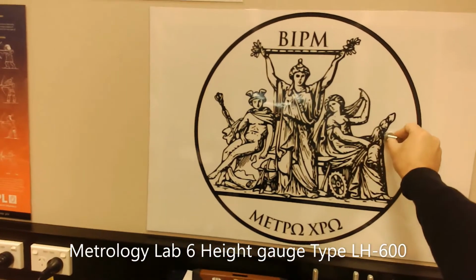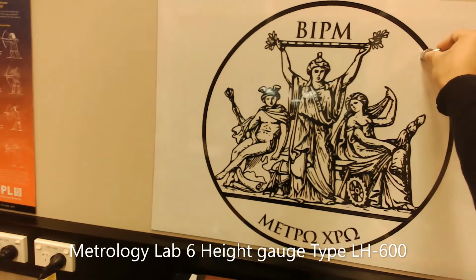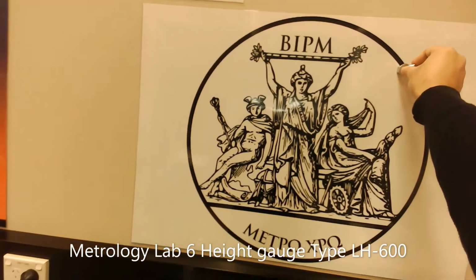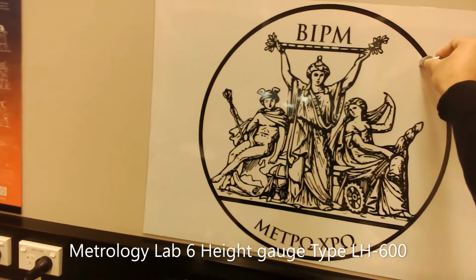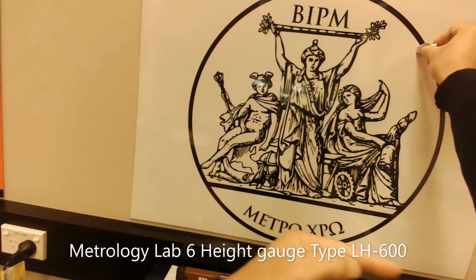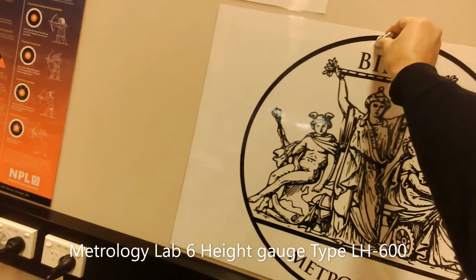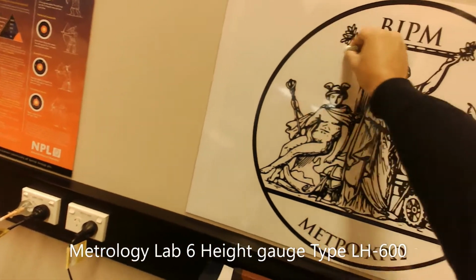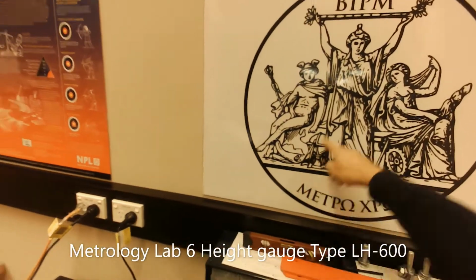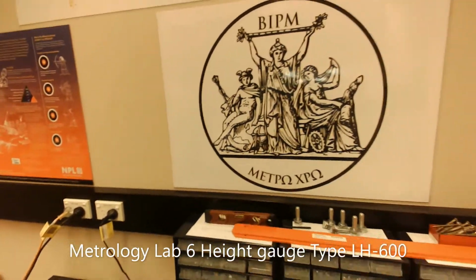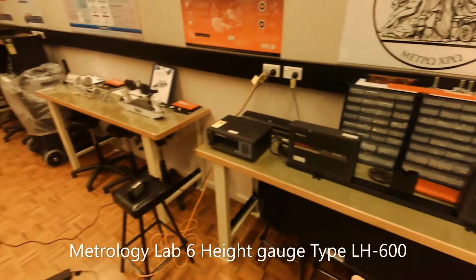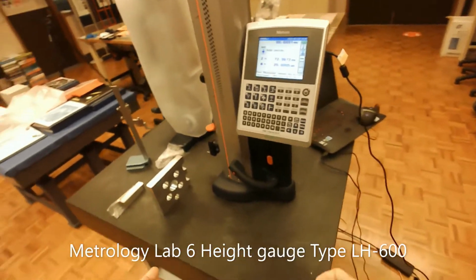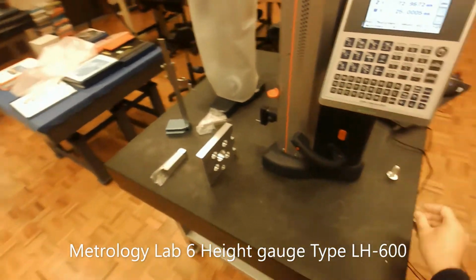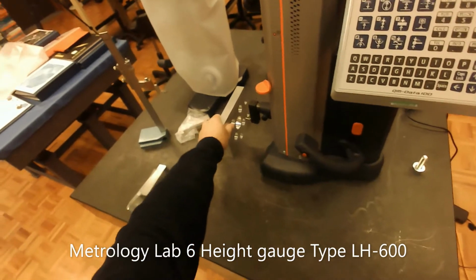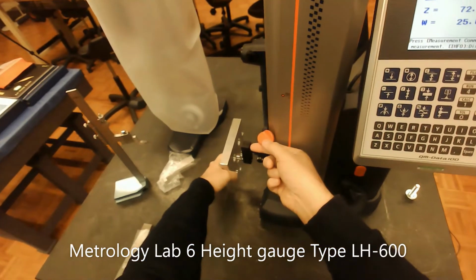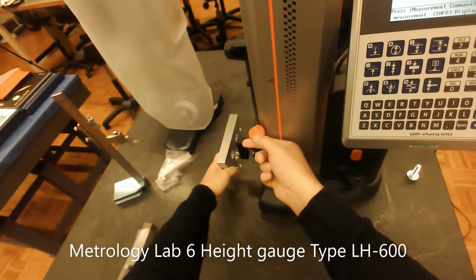The probe will go by itself to the top here. When it attaches to this surface and feels some resistance, you will hear another beep. So you start to push the part in the opposite direction, and the probe will move in this arc until it reaches the same level. You will hear another beep, and it's going to give you the average value for the diameter that has been measured. To show you that, I'm putting the probe at the point I told you about.